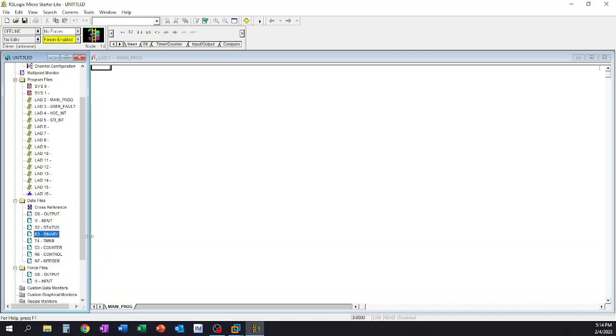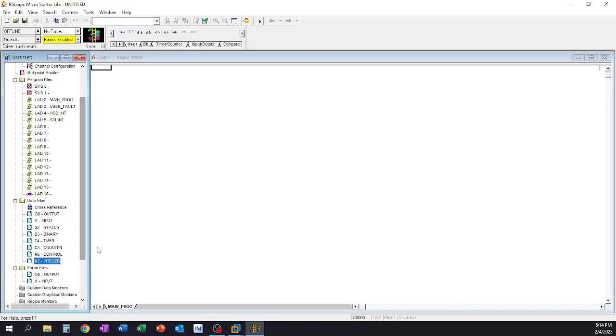And the only thing we have the opportunity to change is maybe like a name of the tag. The tag itself is set. We can't go in. So it'll always be a B3 X number of whatever it is. And that's set. There's no tag creation like we see in Studio 5000 or any type like that. The other one that we are kind of missing in our data files is going to be the, I believe it's an F8, which should be a float. I can tell you it's an eight. I do believe it's an F, but it's a float bit. And so like any real that we would have that would have more than a standard integer of anything that doesn't carry a decimal, that would be in our float file. But anything beyond that, we have to account for that in the float. So in the case of this particular controller, we won't be able to carry a decimal place on a MicroLogix 1000, we'll only be able to carry it as a standard number.